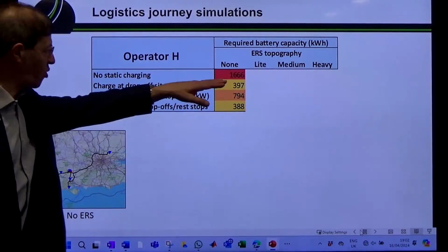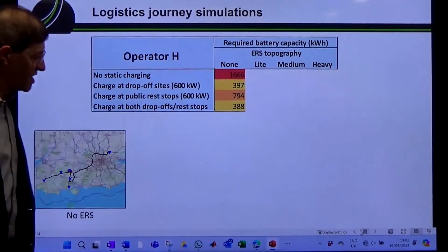So that's not going to work. How are we going to do it? Well, we can charge in different places. We can charge at the drop-off sites, there are 3 of them, where you drop off the load. If you charge for the amount of time the vehicle spends at those locations, at 600 kilowatts, which is a plausible number for a fast charger for a truck (we expect to see them up to about a megawatt or more), you need a battery size of about 397 to 400 kilowatt hours, which is plausible. You can get a battery that size on a truck.